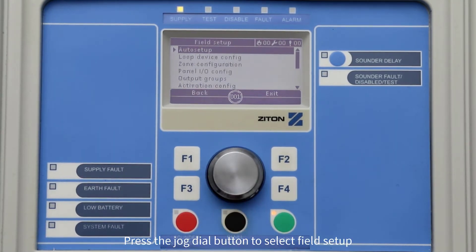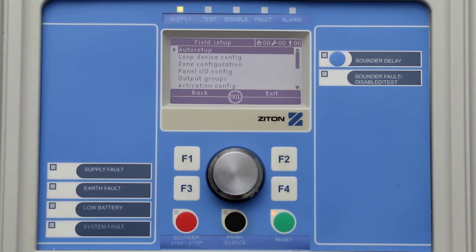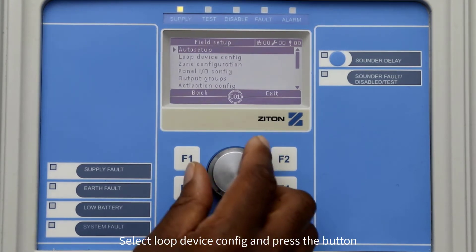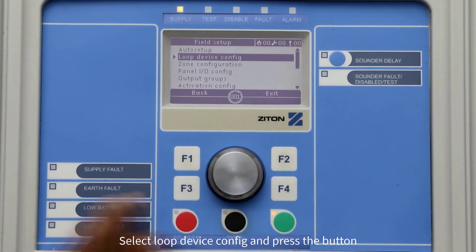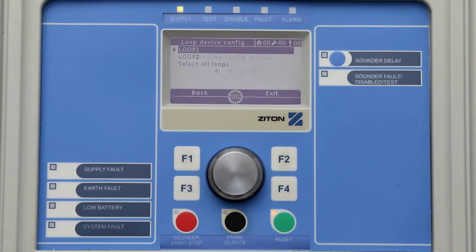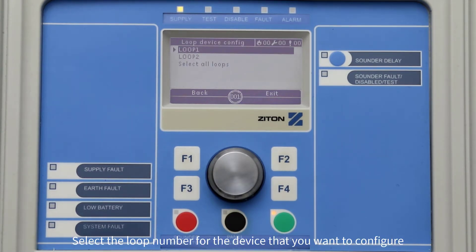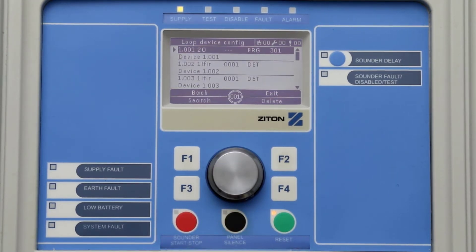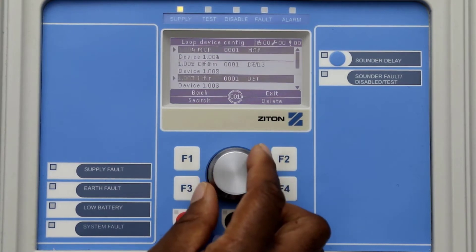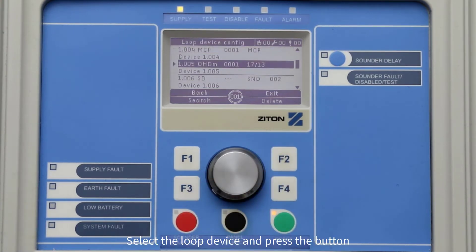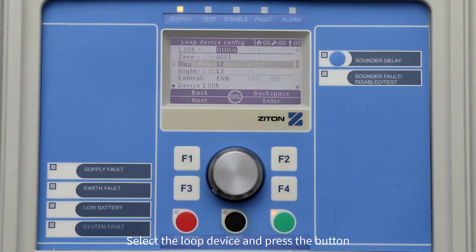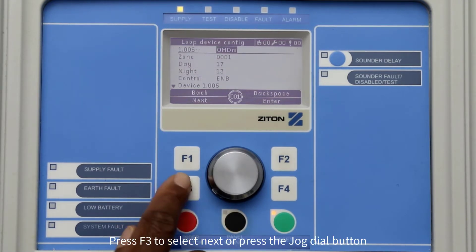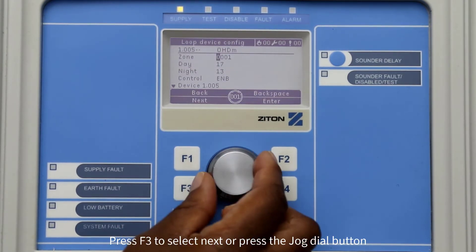Press the jog dial button to select Field Setup. Turn the jog dial button and select Loop Device Config, then press the jog dial button. Select the loop number of the device you want to change credentials for — in this example, loop number one. Turn the jog dial button until you find the multi-sensor you want to configure, then press the jog dial button. Press F3 to select Next or press the jog dial button.